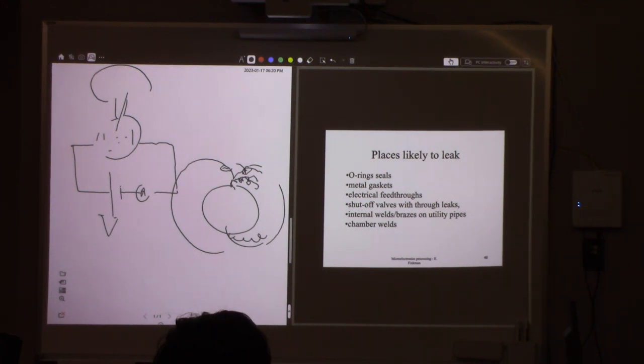So mostly they can come from O-rings, because you can never make good contact with metal and metal, right? So typically we put a kind of rubber O-ring, so that can make a good seal. Or it can be a metal gasket. Sometimes we use copper. If you press copper, it becomes kind of soft, right? So that can make a good contact.